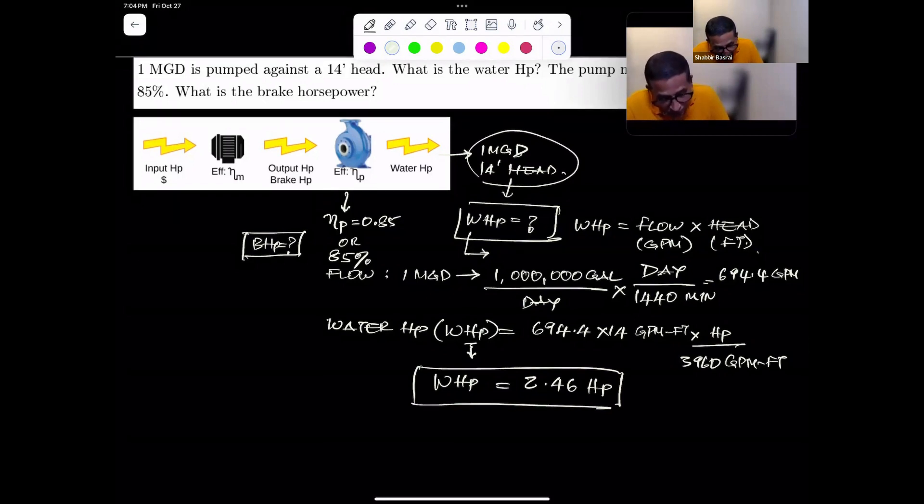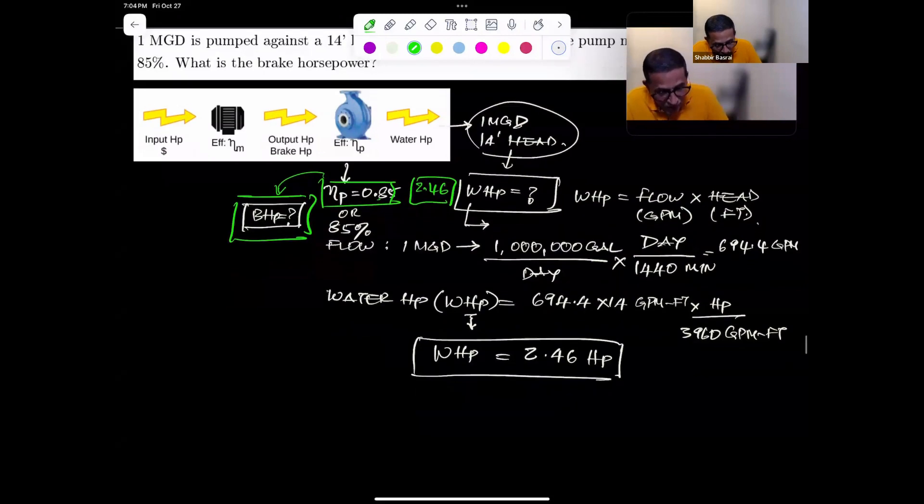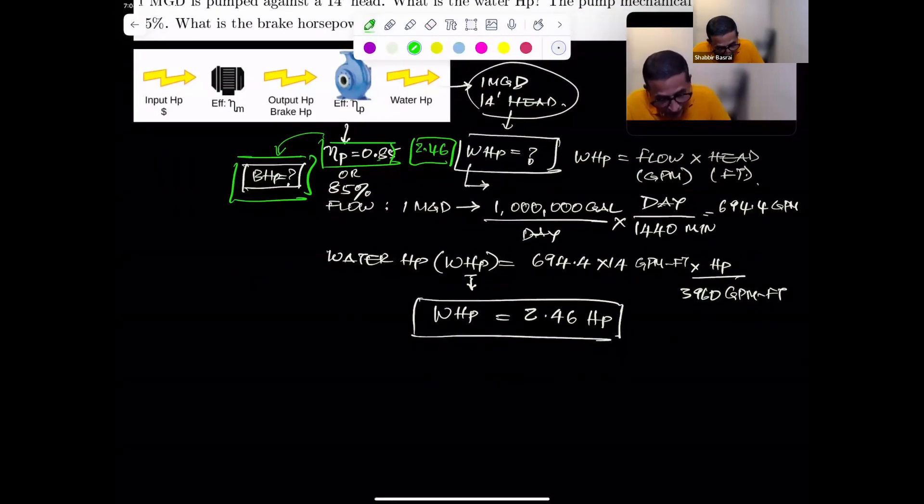Once we get the water horsepower, we know we got this water horsepower as 2.46, and we need to figure this one out. Using these two, we can find this out. We know my pump efficiency is water horsepower divided by the output horsepower or brake horsepower. So my brake horsepower is equal to water horsepower divided by the pump efficiency.